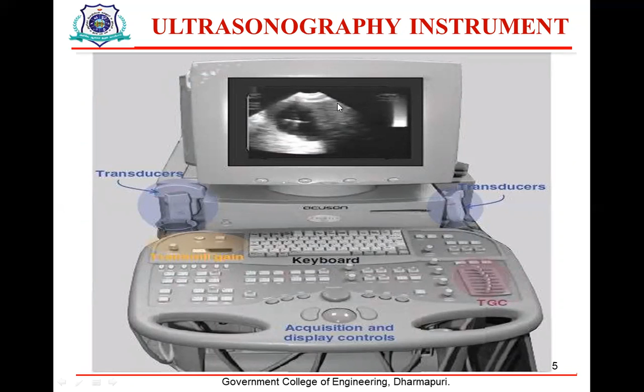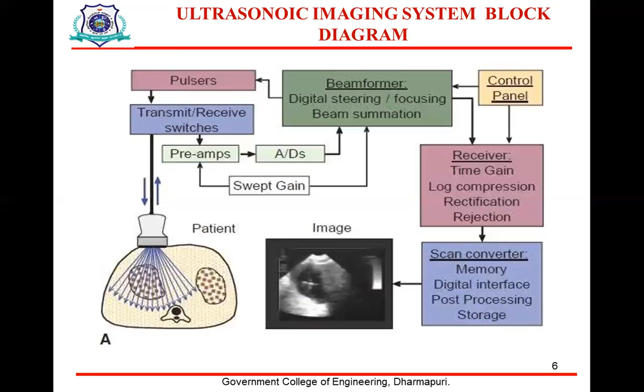So this is the ultrasonic imaging system block diagram. The ultrasonic wave is transmitted to the patient and received using switches, and the signal is pre-amplified and converted from analog to digital signal. Then comes the beamformer, which does digital steering, focusing and beam summation, and it is given to a receiver. The receiver processes the signal with compression, rectification, rejection, and the scan converter. It may be a memory device, digital interface or post processor storage, and the image is stored.